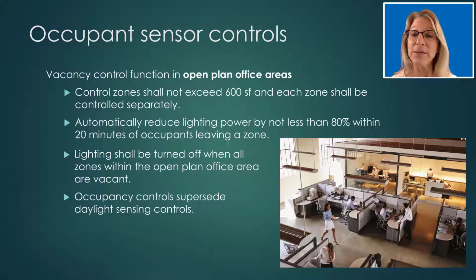Note that occupancy controls do supersede the daylight sensing controls. What this means is that when a vacancy sensor has triggered the lighting in the space to be reduced or turned off, the daylight sensor should be deactivated until the space is occupied again.